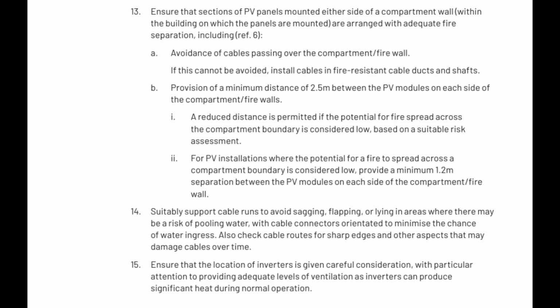Specifically, avoid cables passing over the compartment or firewall. If that's unavoidable, ensure they're installed in fire-resistant cable ducts and shafts. Also, provide a minimum distance of 2.5 meters between PV modules on each side of the compartment or firewalls. This is to create a fire break. However, this can be reduced if a thorough risk assessment shows a low potential for fire spread. In those cases, a minimum of 1.2 meters separation is required.